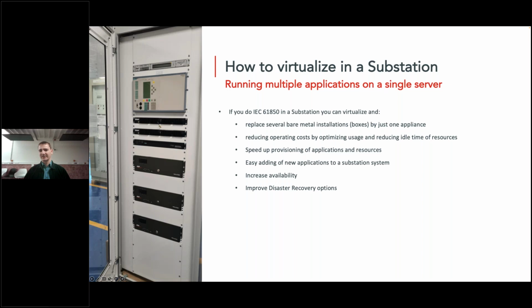In 61850 systems, you can use virtualization to replace multiple boxes like HMI, RTU, merging units or their software, the IDS system (intrusion detection system), and so on. This will definitely reduce cost, reduce unused resources, and help speed up provisioning of the full substation. As Edwin mentioned, in case of repair it will be much faster compared to replacing IEDs and traditional I/O plus computing platforms.